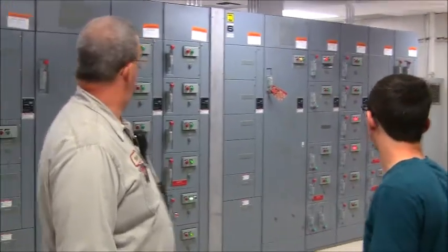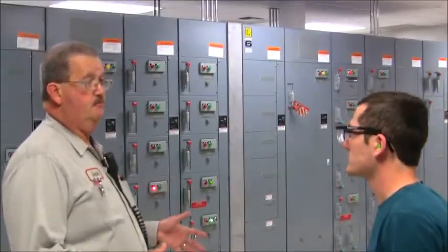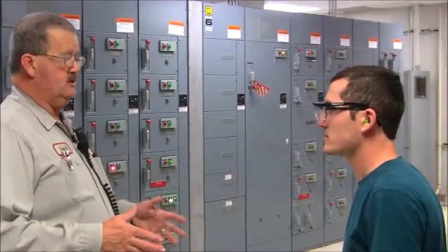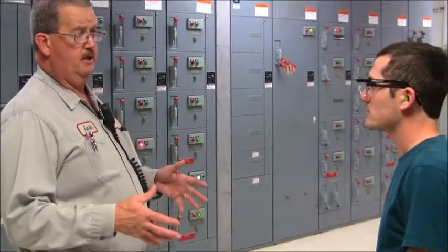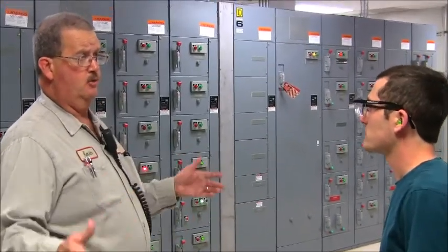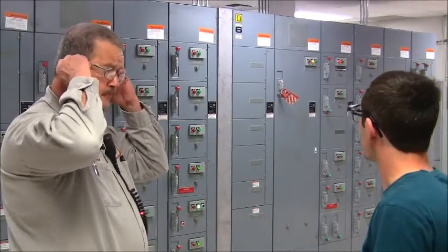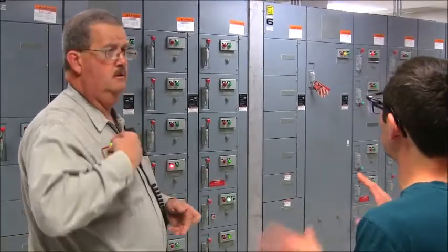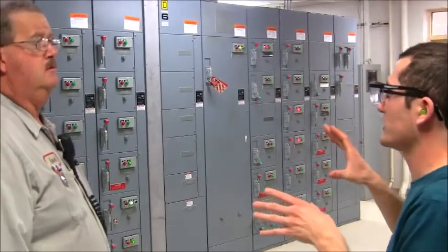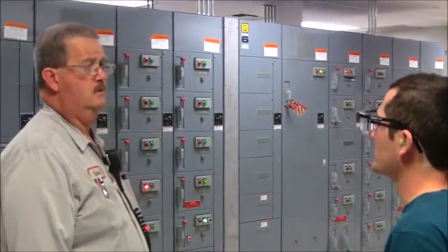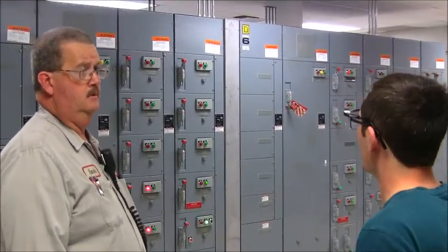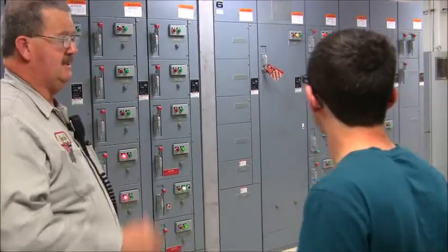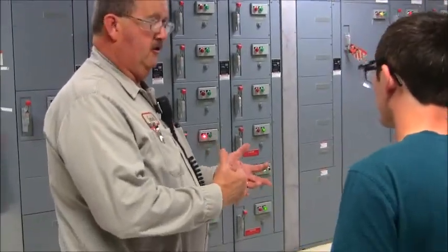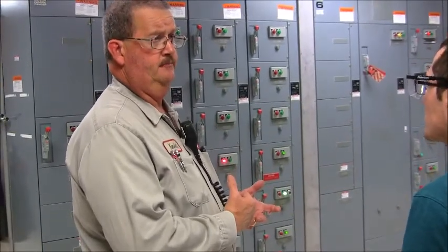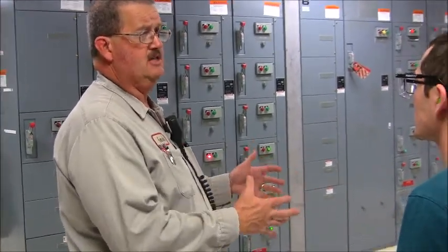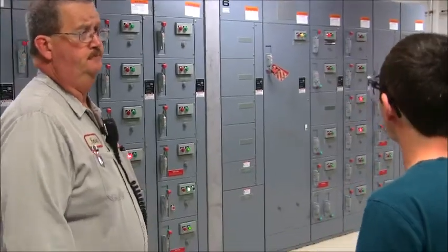Every tag out we have for each system, we tag out the system that takes away the most capability from the plant. That's how far you go with the tag out. So if you're taking something out of service, you're going to take almost everything associated with it out as well? Yes. When you look at that tag out, you look at how far it affects operation of the plant. That's essentially how far you go to be safe.